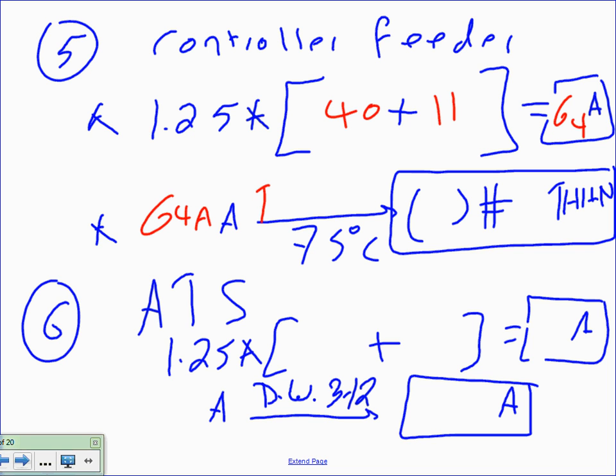Then you take the 64 amps to table 310.15(B)(16). And when you go there, Chris, what do you get? Number six. And let's continue with 3 conductors, number 6, RHW. I don't want to bring up a big topic, but are we pulling ground or EMT? If you put them in the EMT conduit, your EMT will be your equipment grounding conductor. If you don't, then you need to size an equipment grounding conductor based on the overcurrent protection device.